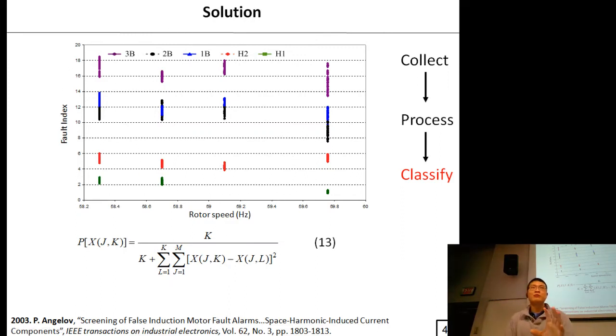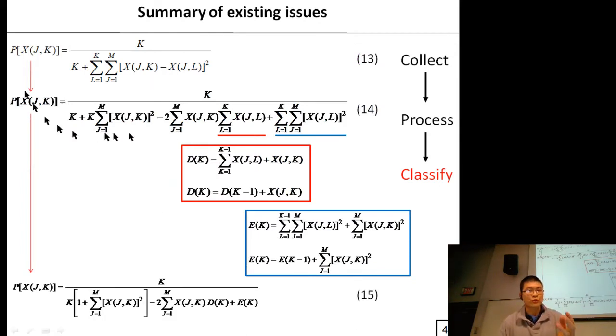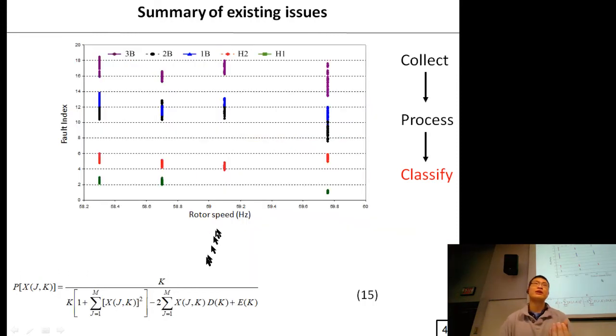However, there is a problem with something like this. Say we collected data from a place for 10 years. We have 1 billion data points and 1 billion more on the way. It's not practical to keep 1 billion data points for every single motor forever. So the solution to that is I derived a recursive form of this kind of calculation so that instead of keeping track of 1 billion values, I can keep track of, say, 10 values and still accurately represent the density of that data as if there were 1 billion.